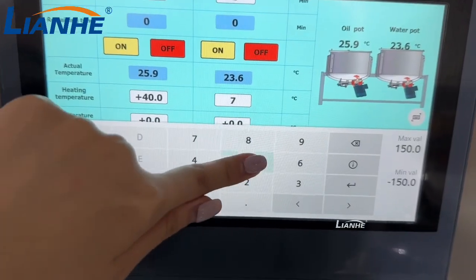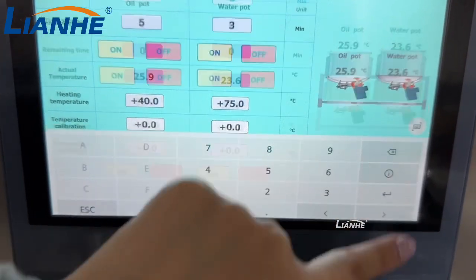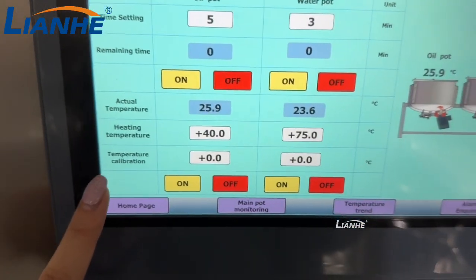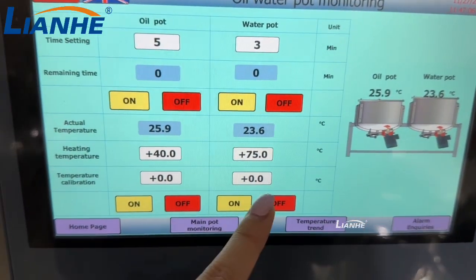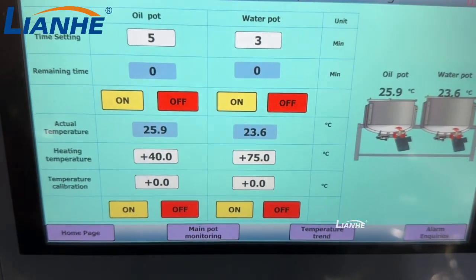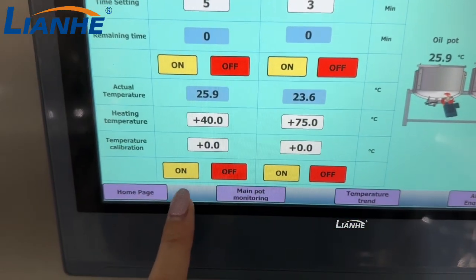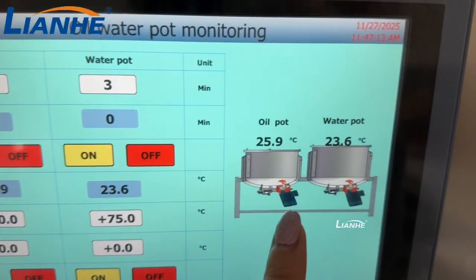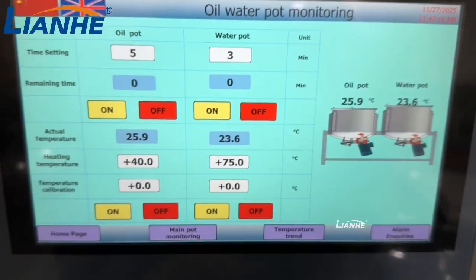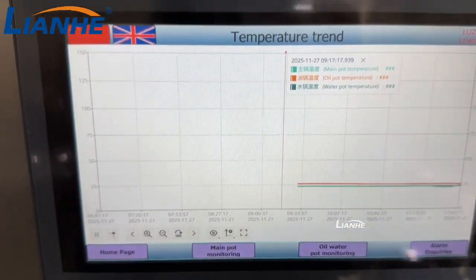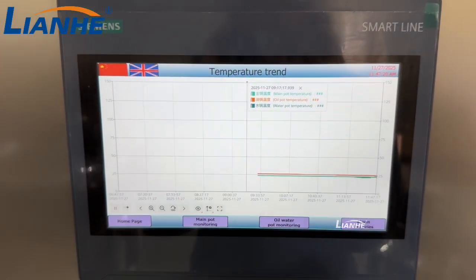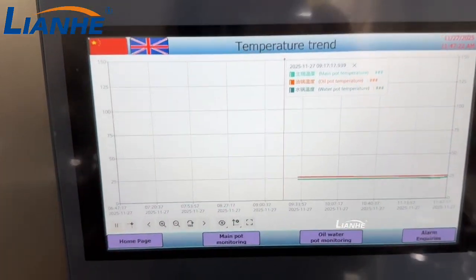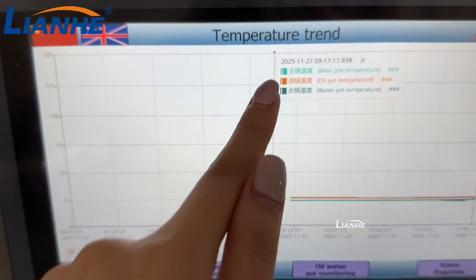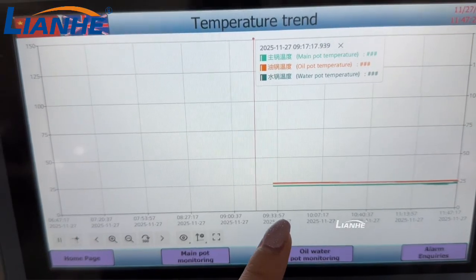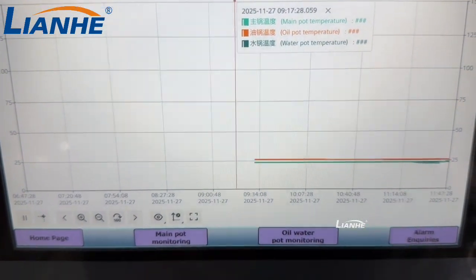And this one, like the 75, if you want. And this is also the temperature calibration, to calibrate the temperature of the water tank and oil tank, and the turn on and turn off function. Now you may check the diagram here. And the temperature trend: you may check the temperature of the main tank, oil tank, and water tank. You can see we have different colors to present it here.